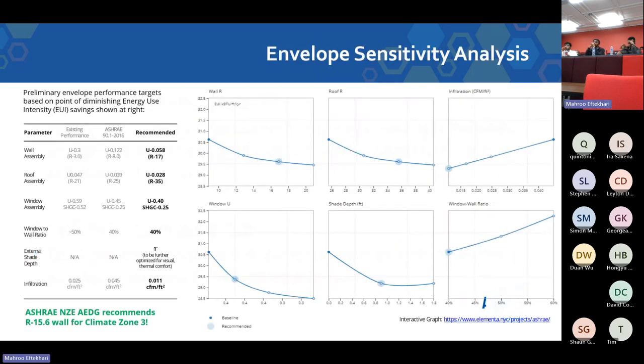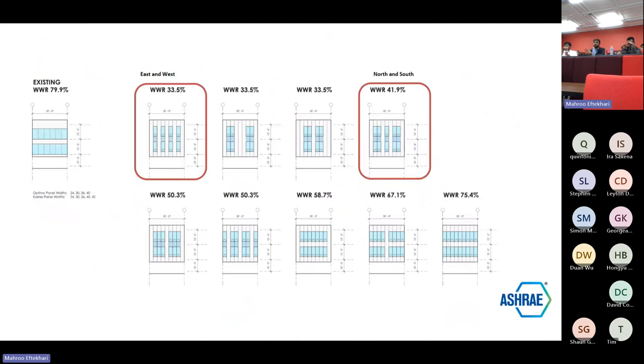The design team did a complete analysis of the existing performance. We used ASHRAE 90.1 as a baseline, even though it's for new construction, then did calculations and recommended wall assembly U-values, roof assembly U-values, window assembly, window-to-wall ratio at 40%, shading on the sides, and infiltration rates - all established through detailed analysis.